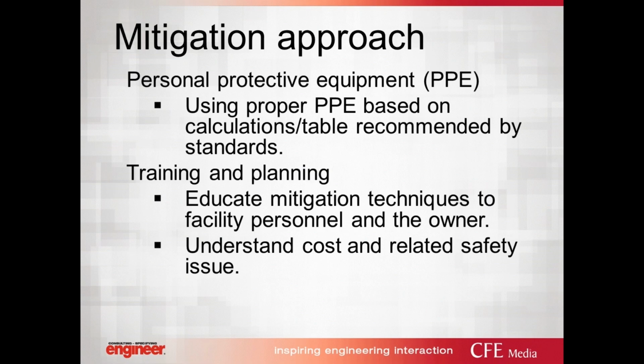Personal protective equipment, which is typically part of the arc flash study anyway, I will discuss when we get to these steps. At the end, you select your PPE, and based on that, you perform the maintenance, working on energized equipment. Therefore, PPE, based on the latest IEEE standard, which I will explain again at the end, you will select based on the incident energy calculation, and be ready with proper PPE.